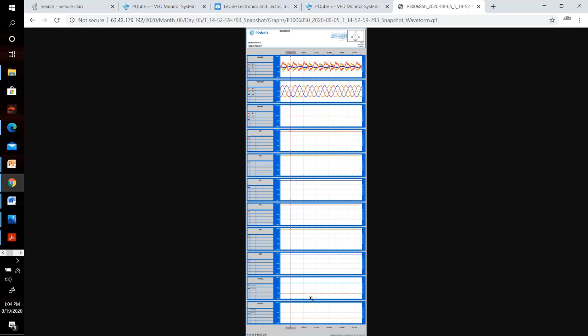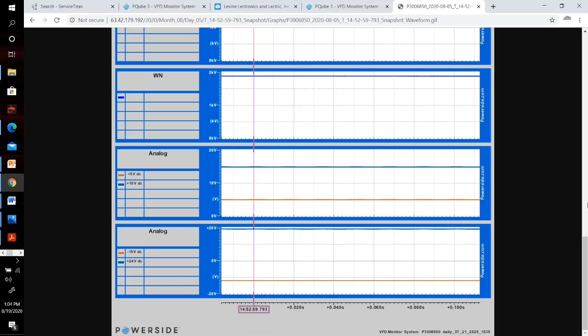So some of the things I mentioned: the drive scan will store up to 2 years worth of data in the drive scan itself, on this hard drive. If I go back, I can look at what happened on the 5th on this drive, and if I click on this it gives me each occurrence of a problem, or a snapshot, with all this data. For example, I can look at the waveforms of the drive, the DC bus, the power supplies, and all of that. I can go back and look at what happened on what day and what time. So this is all data that is readily available in the drive scan.